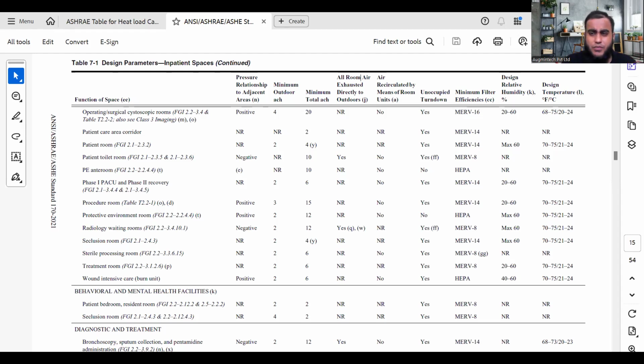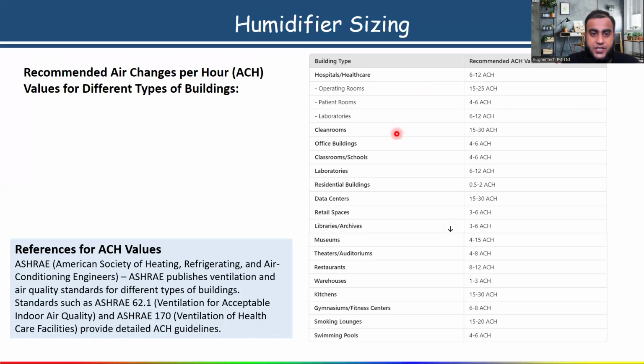So from here, from ASHRAE 170 or ASHRAE 62.1, you will get all this detail. Okay, ACH value. Okay, so here I have taken some recommended air changes per hour values given for different types of building. For example, suppose if you are designing for an office building, here they have given 4 to 6 ACH you have to maintain. Okay, all of you. So this is all about it.